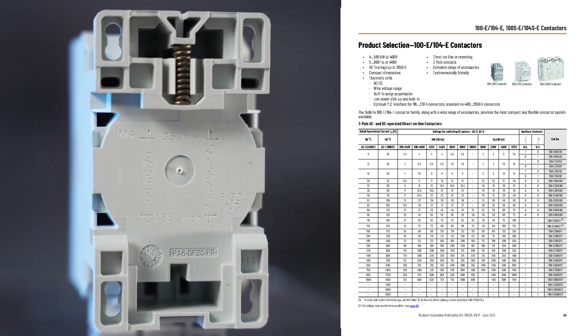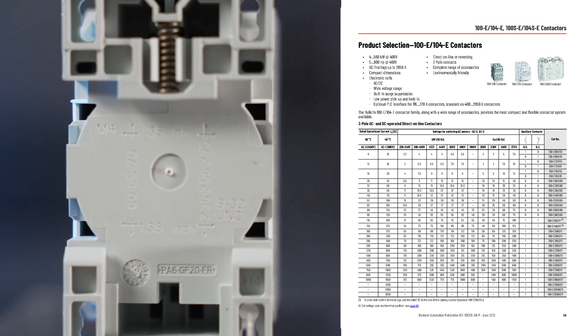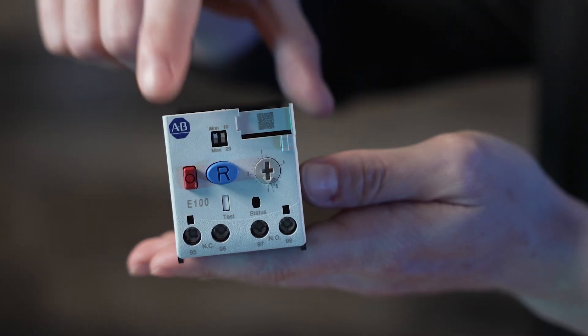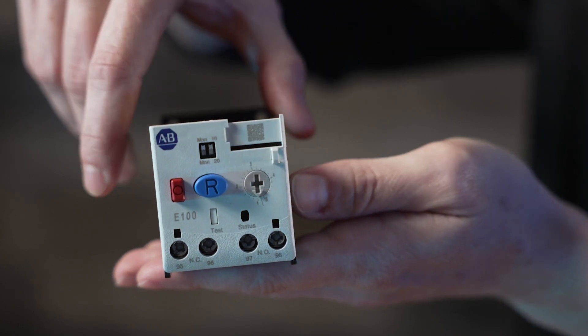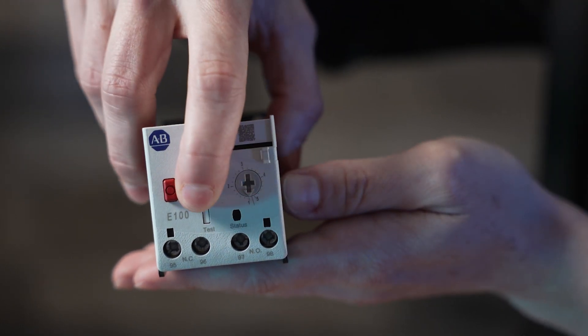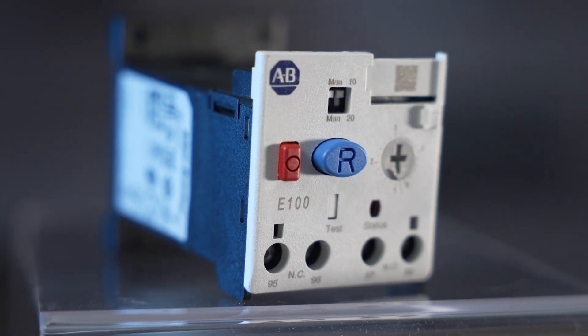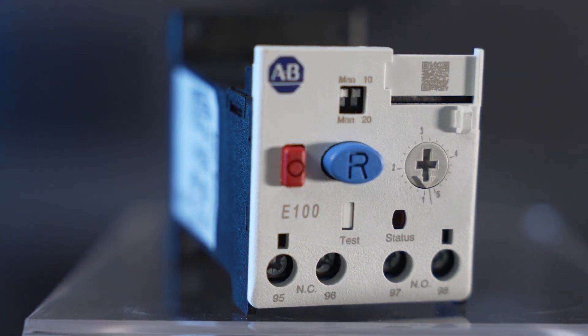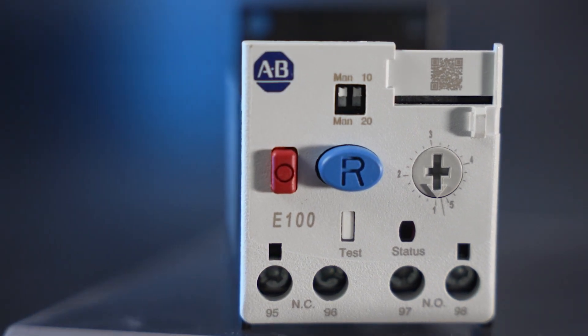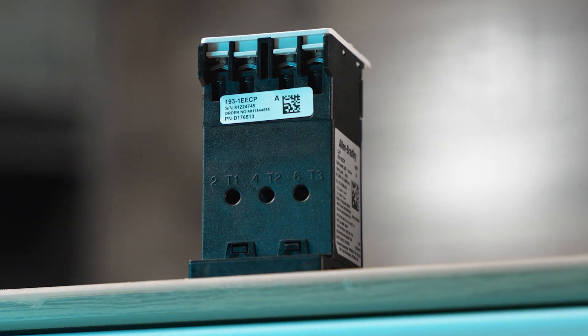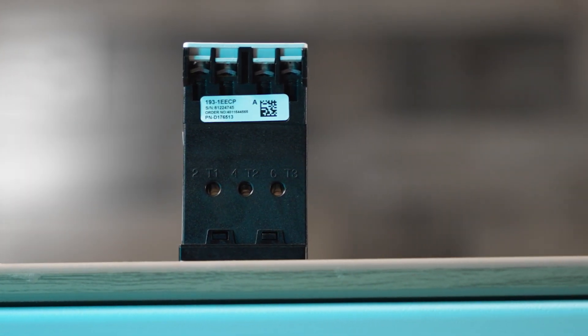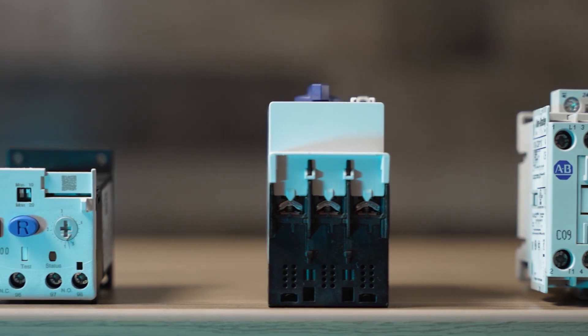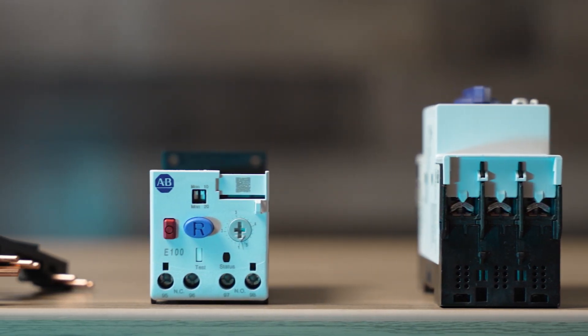This sample kit includes a pass-through E100 overload, so wiring simply passes through this component. However, there's another version of the E100 overload that can directly connect with the 100E. These are manufactured with a bus bar type connection, not unlike the accessory modules of this kit, to eliminate the need for wiring. The components simply fit together and then the installer just tightens the contactor's terminals to secure it. The direct connect option for the 100C contactor has been available for some time, but the 100E direct connect option is fairly new.